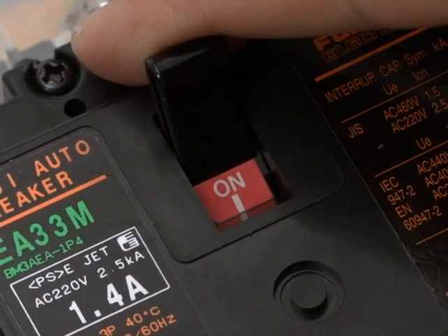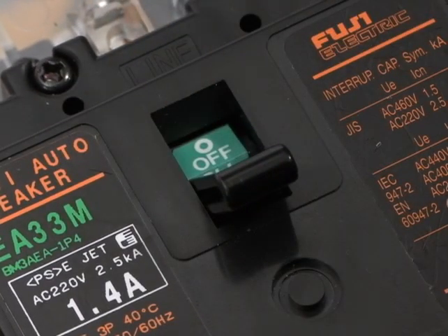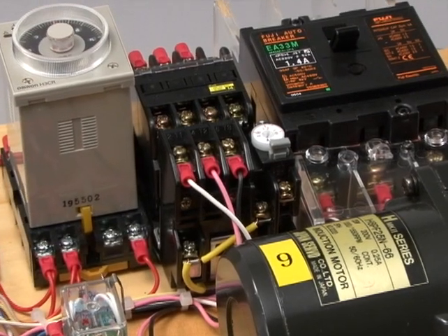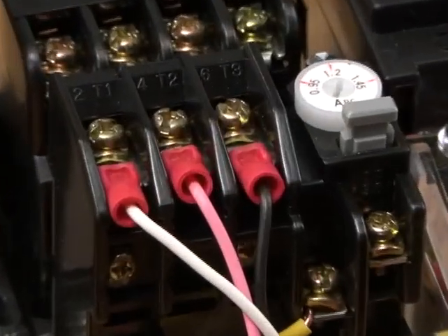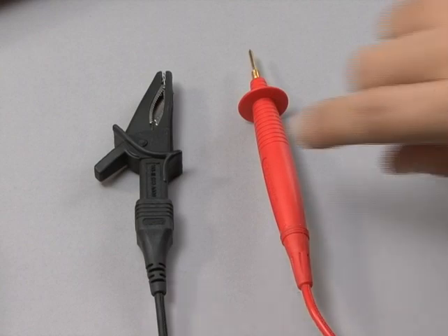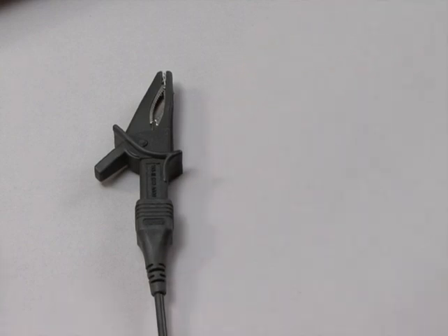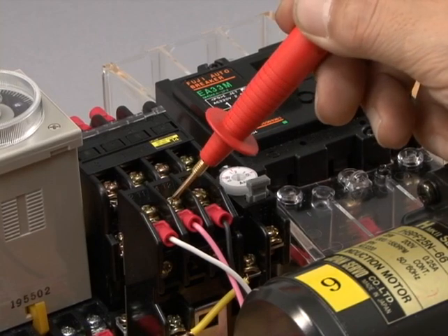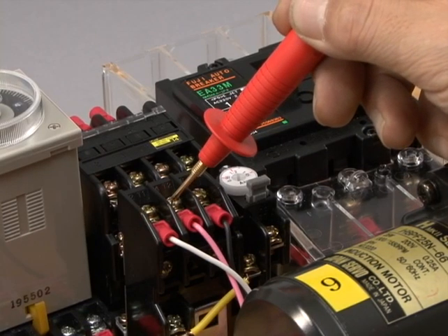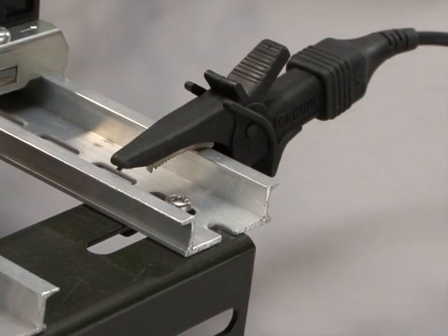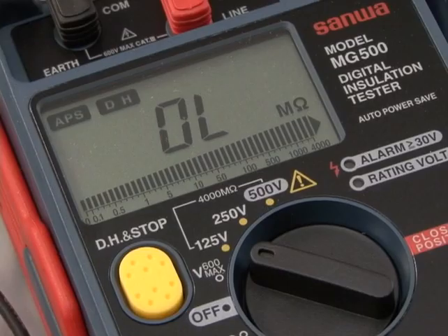Before measuring the insulation resistance, turn the MCCB off. Unless the motor is dismantled, the coil will not be visible. However, insulation resistance can be measured at the MC output terminal because the motor coil is electrically connected to the MC. So, use the megger's plus side test lead, red, to touch the MC output terminal. Use the other lead, black, to touch the ship's hull or the terminal to which the motor's ground wire is connected.